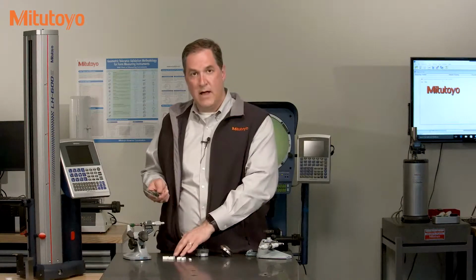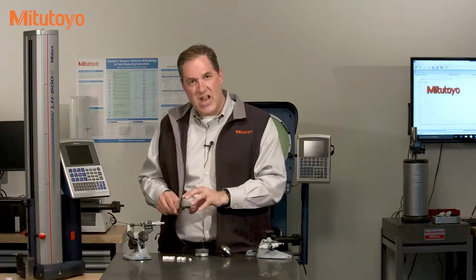But when it comes to measuring instruments, like this micrometer, or this caliper, or this indicator, or these gauge blocks, calibration is really about a search for errors. We want to develop a calibration method that efficiently hunts down and finds any potential errors in the measuring instrument. A good calibration mitigates the risk of measuring instruments not performing as accurately as expected or required.